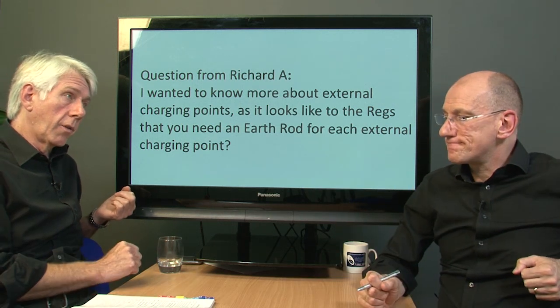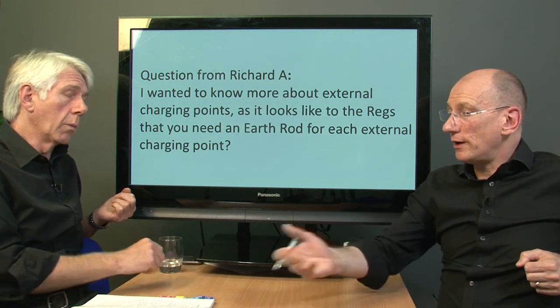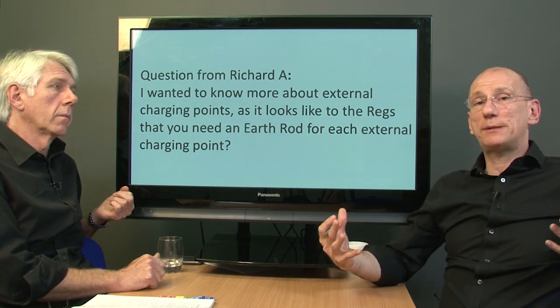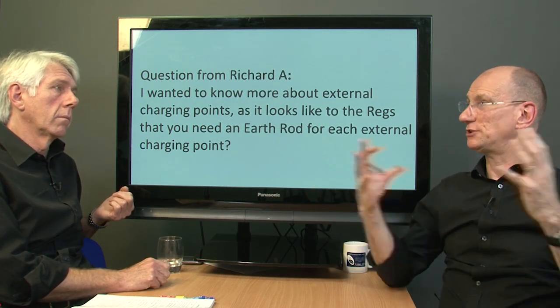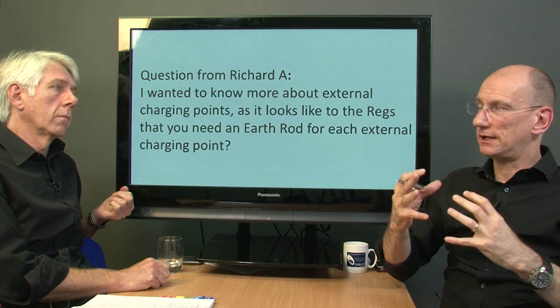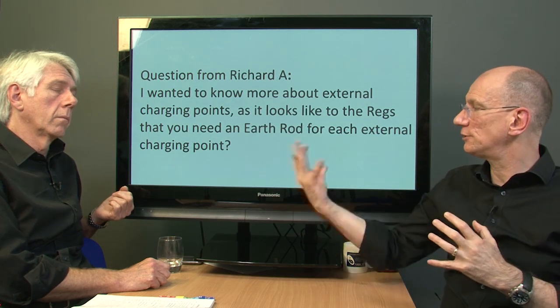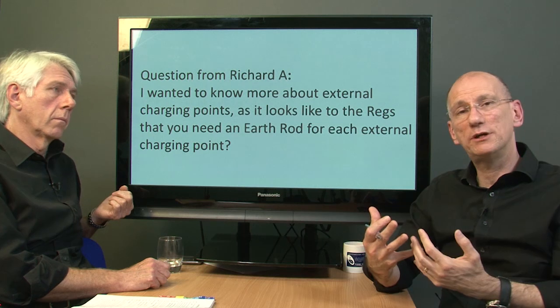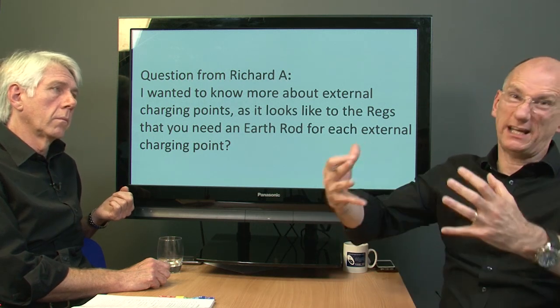And in the event of option 3 with the piece of kit - if you're going to use the protective measure of electrical separation, this is complete - I won't say isolation - but basically the primary is separated from the secondary, so you wouldn't need an earth electrode. There is no return path. But it gets big, it gets expensive.